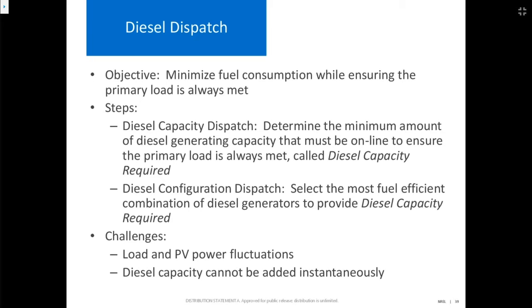The requirement is that if one goes down, the other needs to be immediately available, so spinning reserve. In the case of the cube, since we have this novel synchronization and paralleling capability, you can count the battery or the cube source as the spinning reserve, but nothing's spinning, and we're not consuming any power. So you get the benefit of that spinning reserve sitting there that also has other functions, such as augmenting power. You can shave peaks so you don't have to turn on that second diesel generator. If your load goes above, say, 60 or 30 kilowatts, you can pump out some battery power or solar to meet that load demand without turning on another diesel.